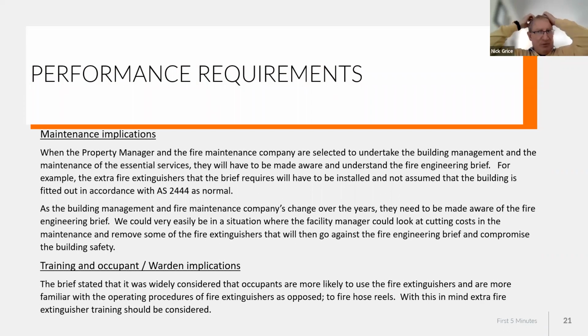So that's where we come in with the first five minutes, where you have a look at the brief. Yes, it said take the hose reels out and they put extinguishers in. Now the problem you got, or did get a few years ago, is some buildings went in not knowing whether there was a fire engineering solution in there, something like this.